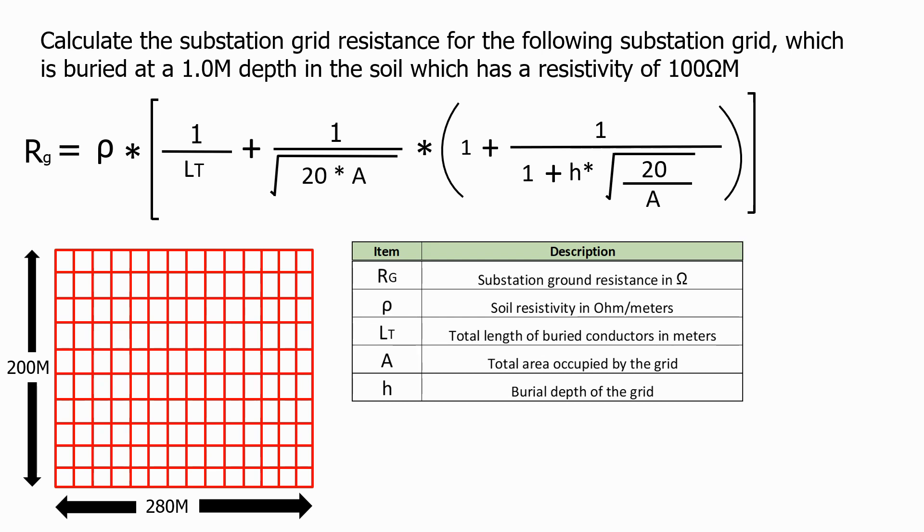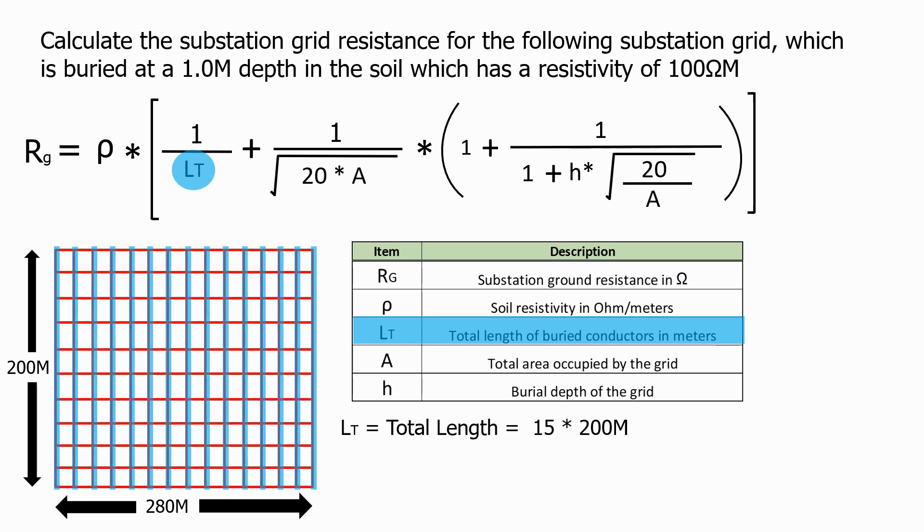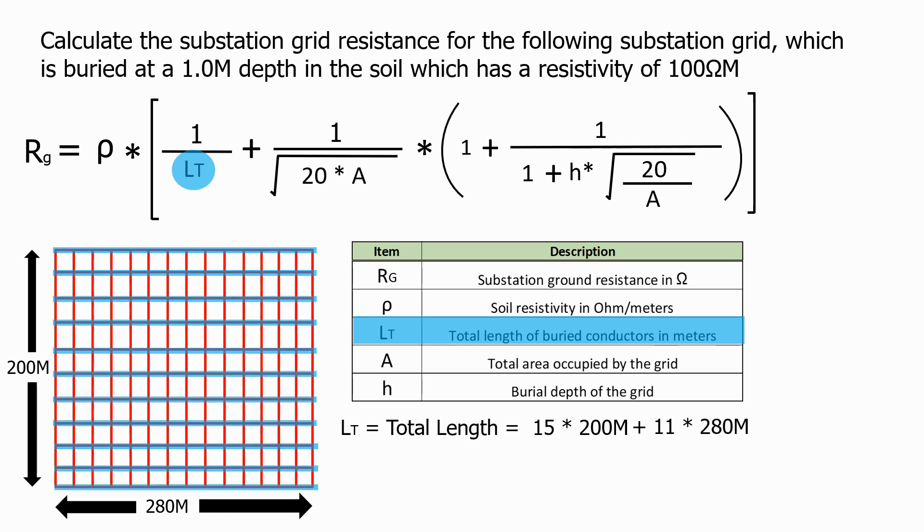Firstly, we need to develop some calculations. The first one is Lt, which is the total length of buried conductor. Looking width-ways, we have 15 conductors all with a length of 200 metres. Looking length-ways, we have 11 conductors all with a length of 280 metres. Which gives us a total buried conductor length of 6,080 metres, which is a lot of expensive copper conductor.